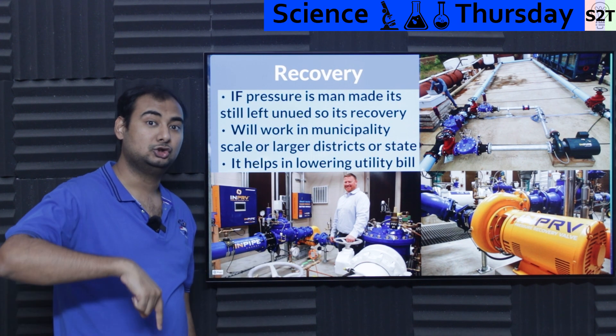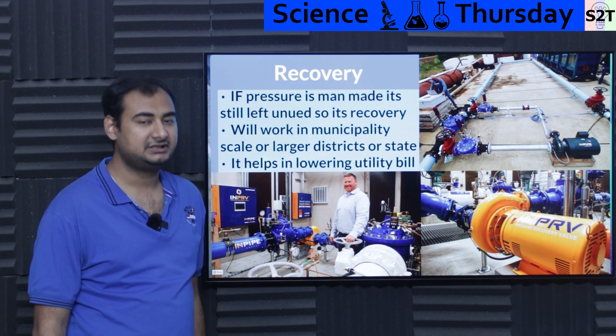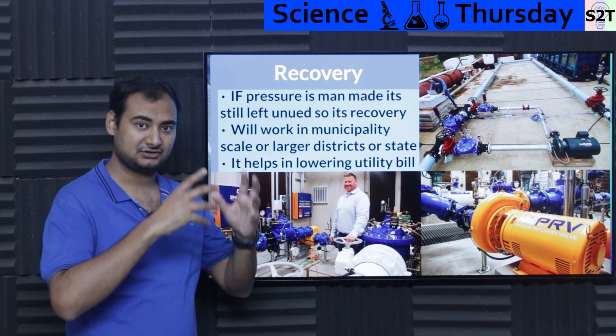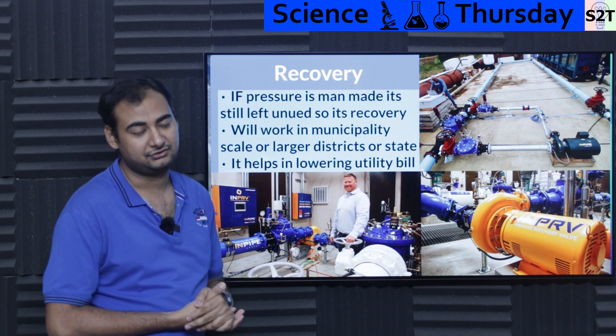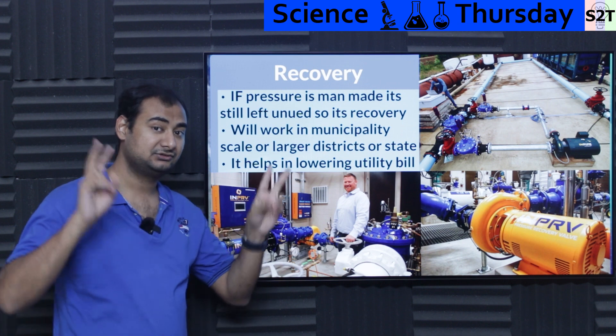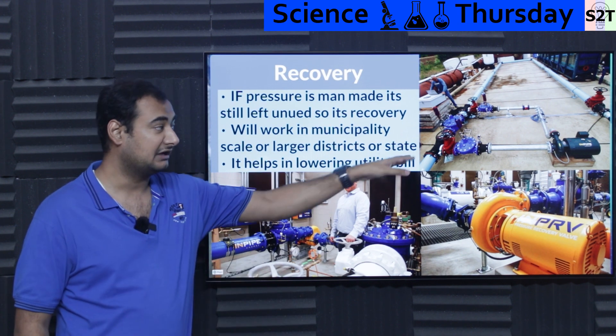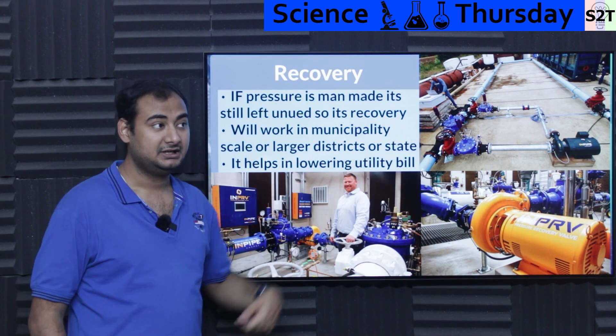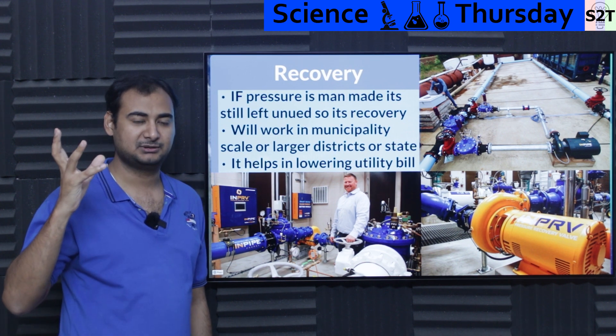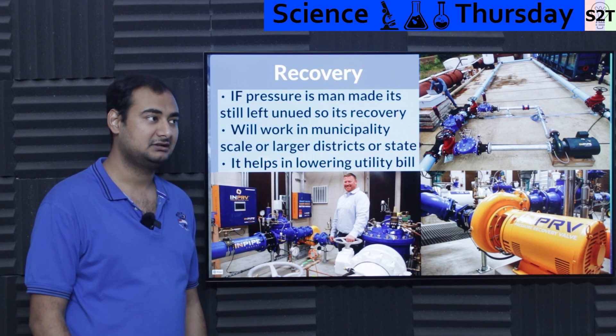It can also be done for ludicrously tall buildings — if you are taller than 20 stories, you can do serious energy recovery. If your water pumping cost to the top of the building is one megawatt, you can literally halve it. Energy recovery is a valuable tool, and the ROI on this equipment is surprisingly quick. It's one of those lightbulb moments: what if we extracted energy here rather than just wasting it? It actually makes sense.